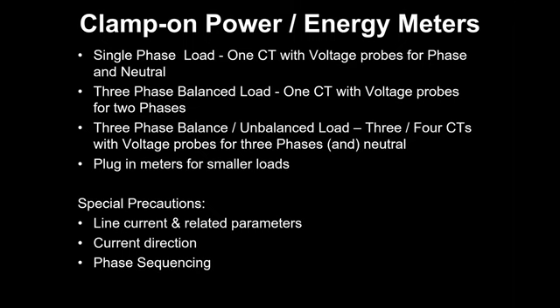There is another meter which is used for smaller single phase loads, the plug-in meter. I think Ashok showed it towards the end of the slides. You just plug it into a socket. The meter also has a socket through which you connect your cable and load. So it will show you all electrical parameters, and you can note them down. Like we do when auditing, say, air conditioners, or when you want to know the power consumption of an oven, mixer, or anything else, you can just use a plug-in meter. I think now it's available on Amazon also, and you can do the measurement.